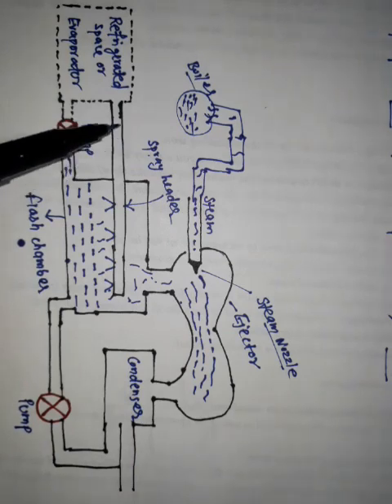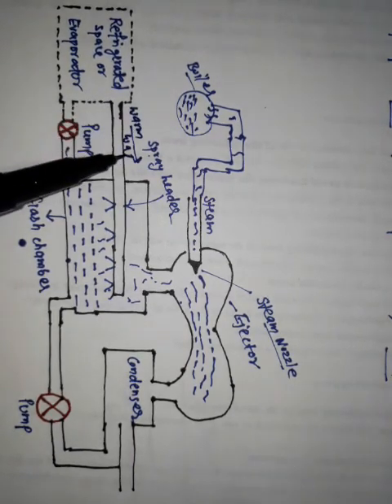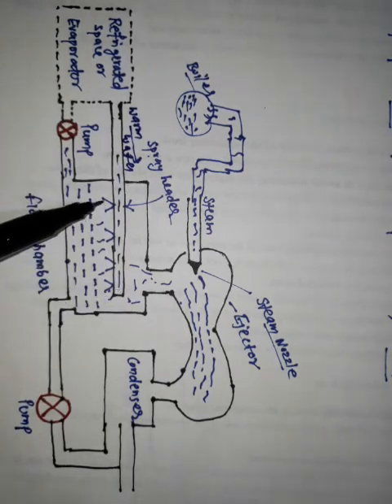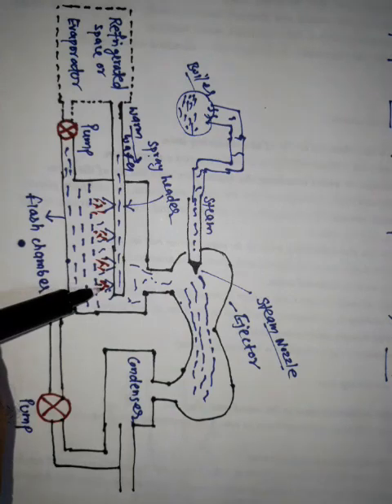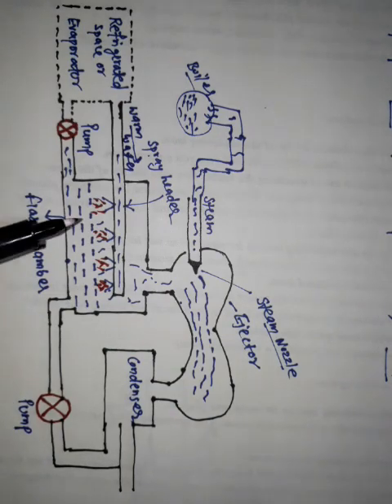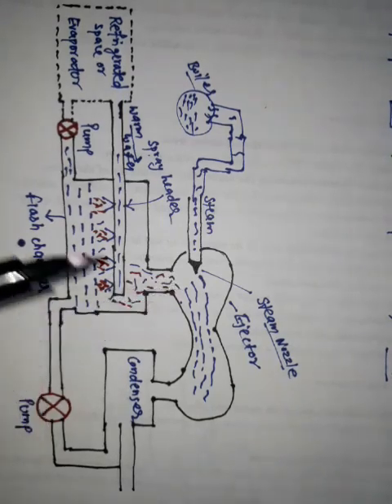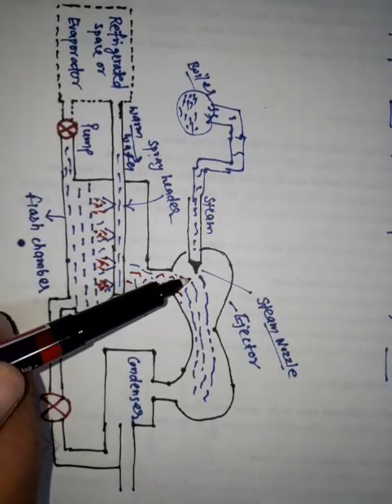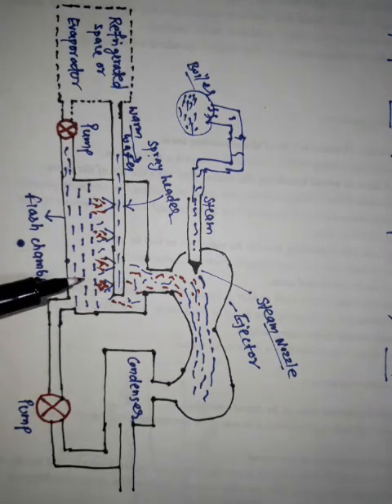The warm water comes from the refrigerated space, and when this water is sprayed through the spray nozzle, vapors form due to evaporation. The vacuum created by the high velocity steam sucks the vapors from the flash chamber and also reduces the pressure.